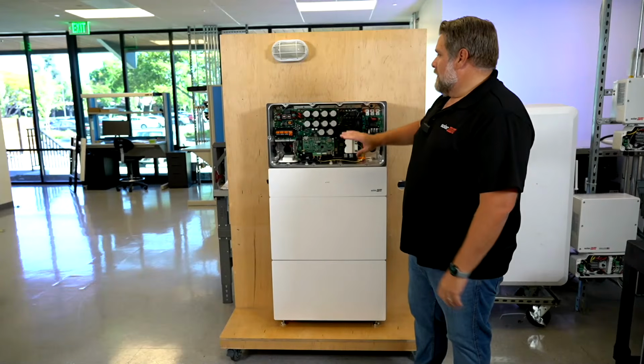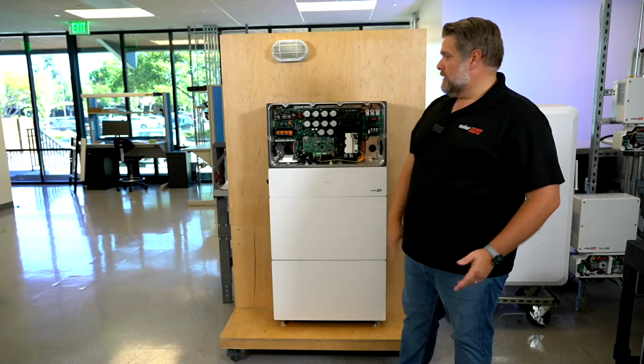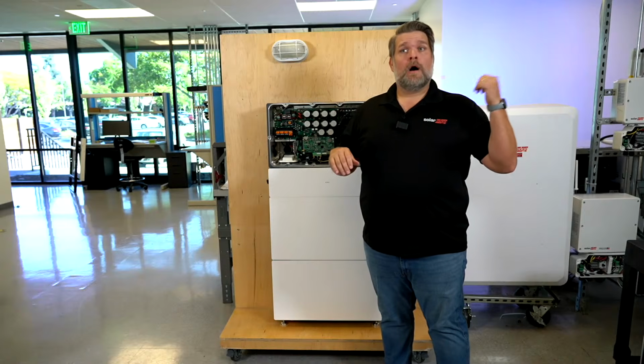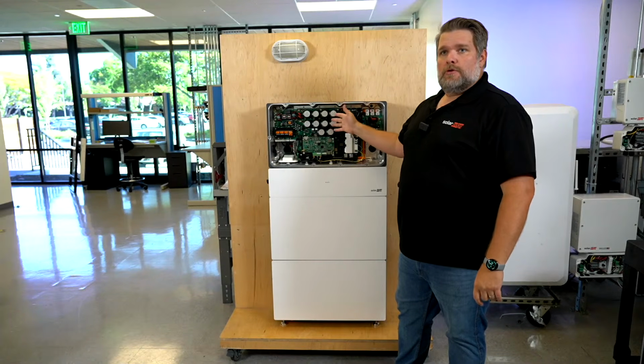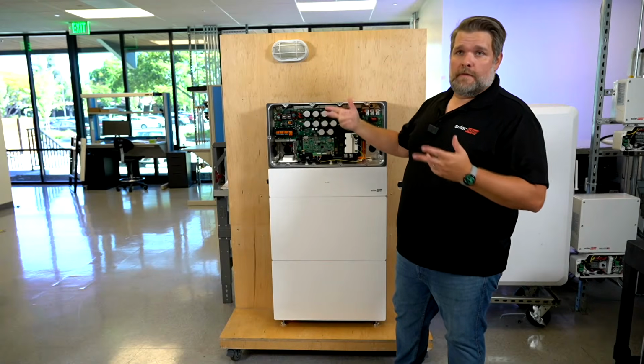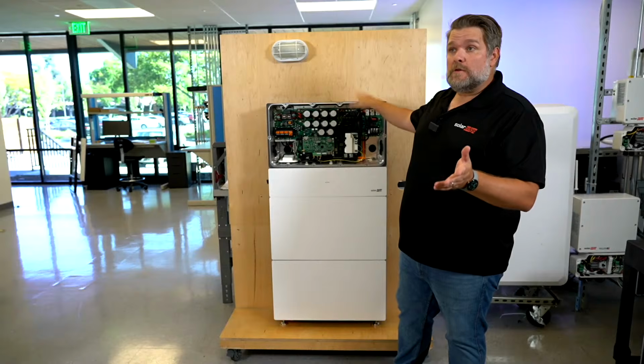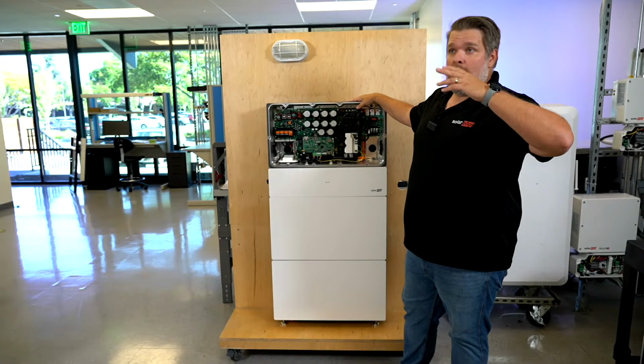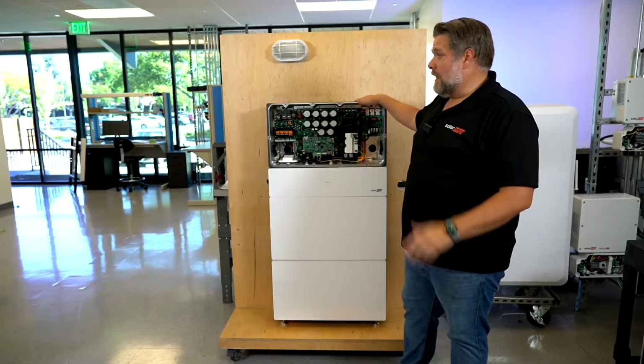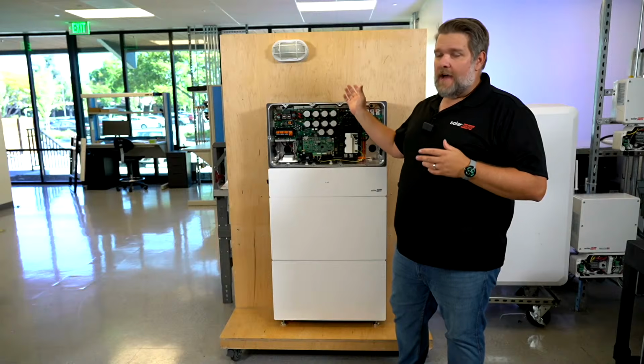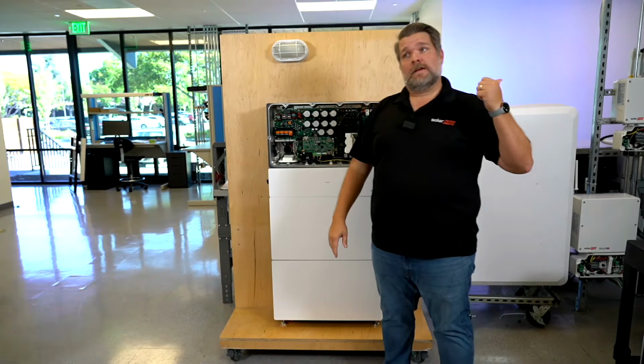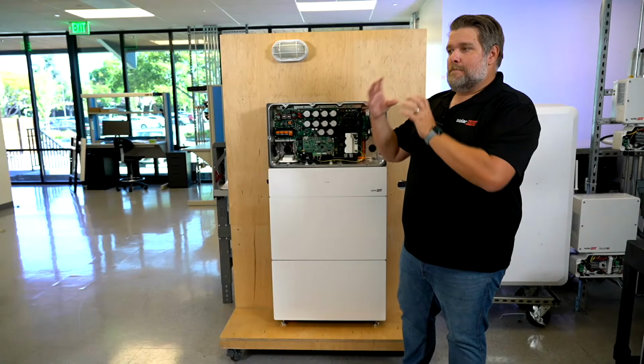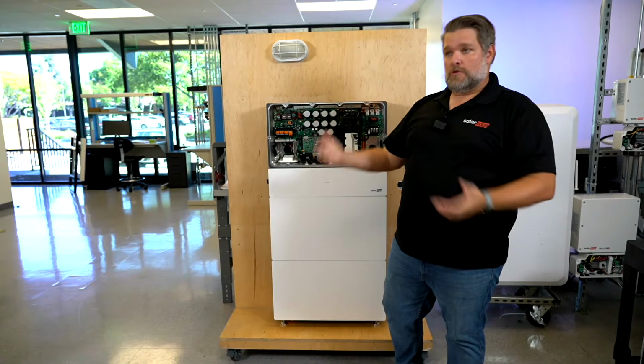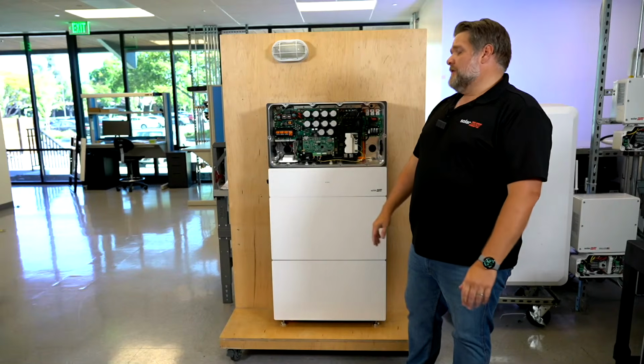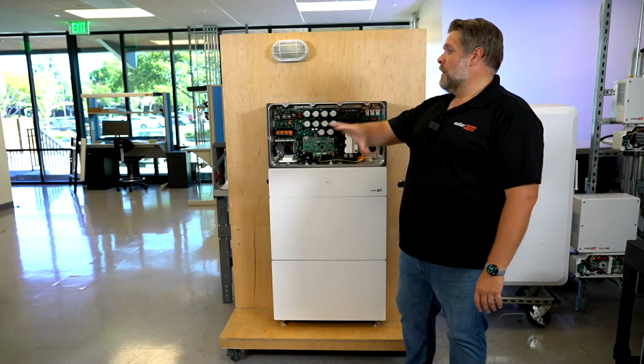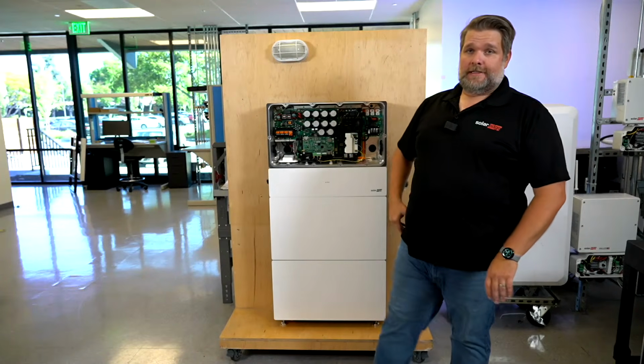The meter collar only works with Nexus because the switching topology and how we get DC to AC conversion is different than HD Wave and the Home Hub inverters. We create a neutral here - this is a 120 volt output, with two of them making 240, which is what most homes are. We also operate at 208, so this will be able to do 208 backup too, for those of us in condos or apartments. So the meter collar just has a switch that electrically isolates the home. The backup interface, because of the Home Hub switching topology, needs a big copper auto transformer to create the neutral for that 120/240. So to answer your question, no - the Nexus Islander only works with Nexus, it does not work with our current technology today.